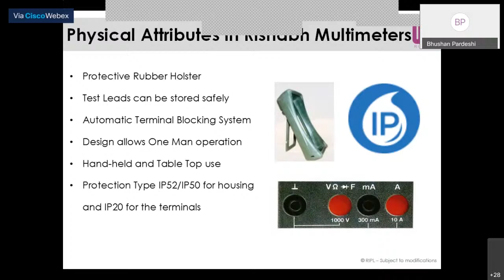The third thing is automatic terminal blocking, in short called ABS. You can see the automatic terminal blocking system. It prevents incorrect connection of test leads and incorrect selection of measurement quantity, which provides safety to the user. So while measuring the voltage, if your switch knob is towards the voltage position, you can see in the picture, the down picture, for example, if you are measuring the current, then your common terminal and milliampere current terminal is open. Okay, it automatically blocks the voltage position and ampere position.